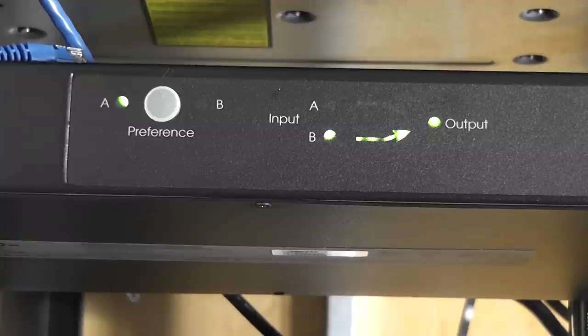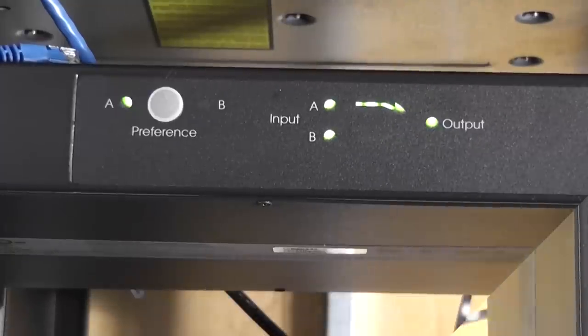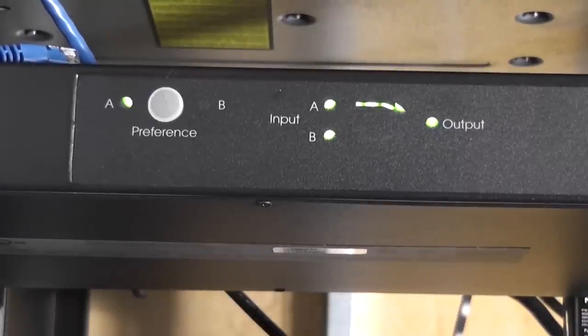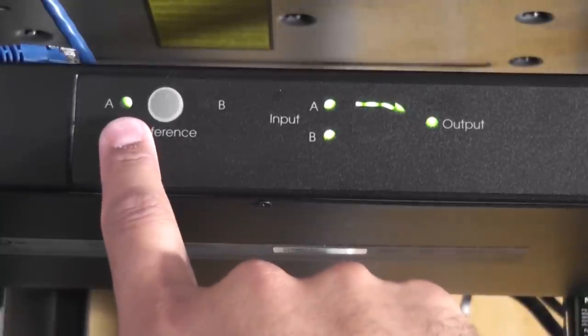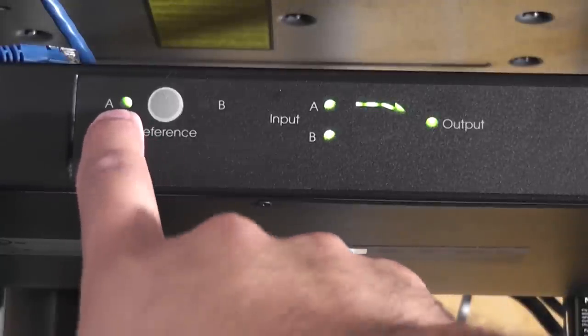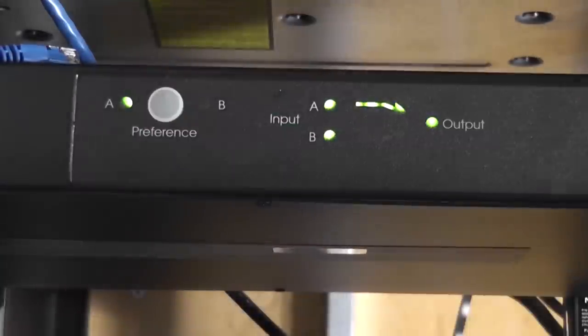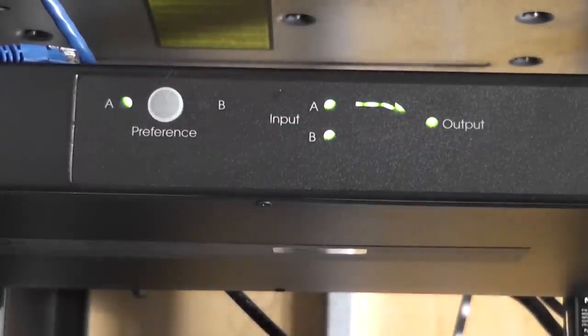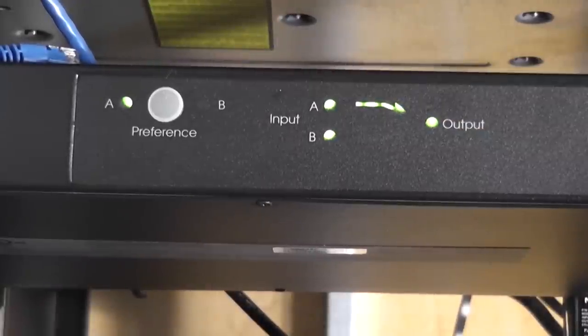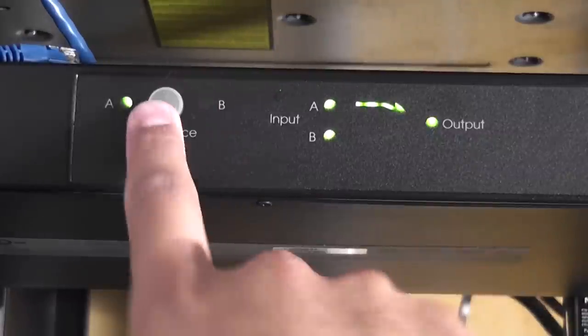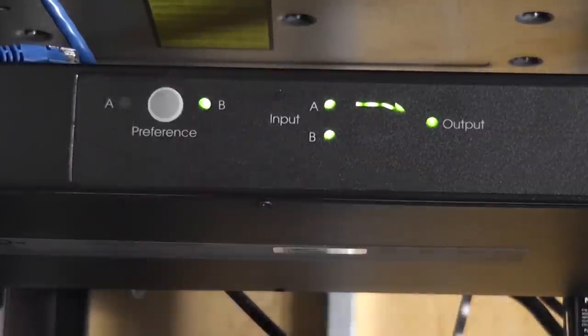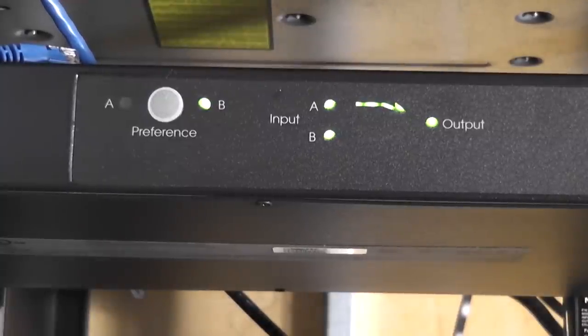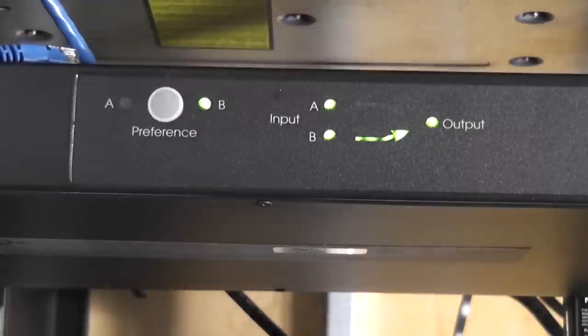All right, one last test. So both units are on. My input preference here is A because that's the 2200. Say for example I want to turn off the 2200 because I want to do work on it or whatever. I can actually hit this preference button here and then you'll see that click over and now input A is not active, so I can actually then turn it off and be all set there.